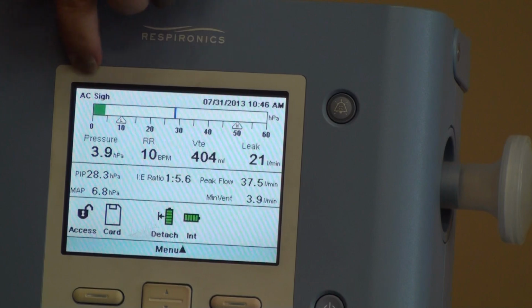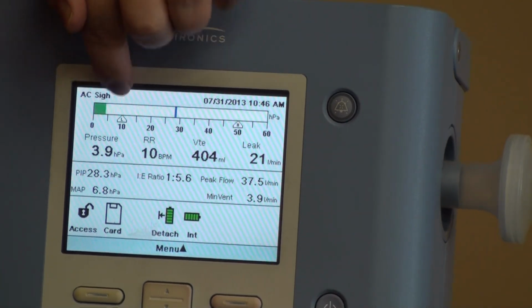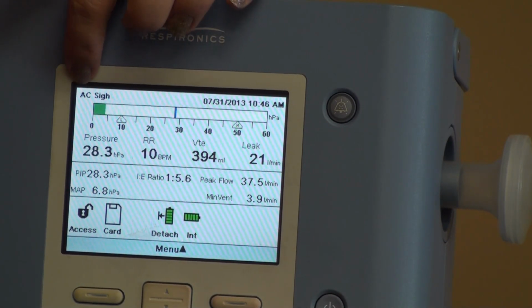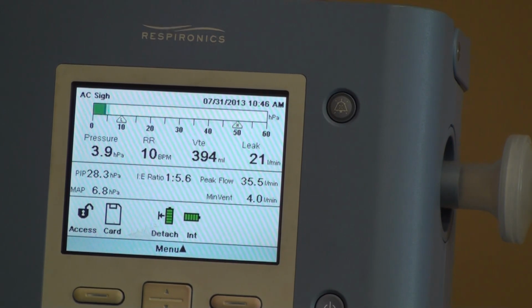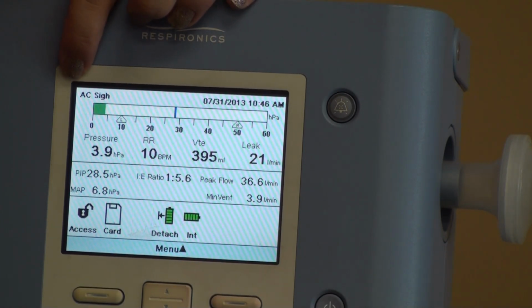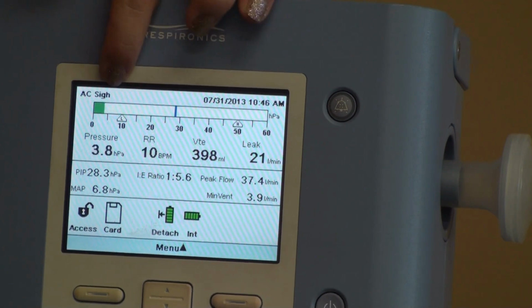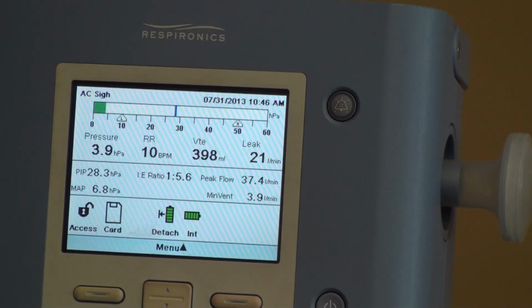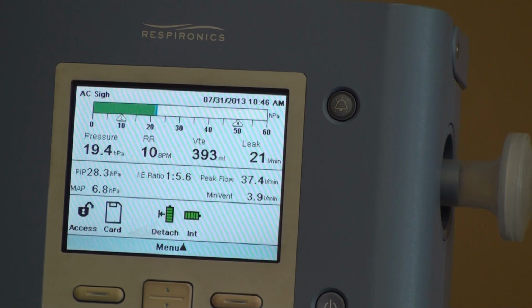B is going to be your prescription. That is this little piece over here. Now I have only one prescription in there. If I had more than one, because this machine has the technology to have 2 prescriptions, you have a primary and you can have a secondary. Your primary can be your main one that maybe you use all the time, and your secondary one might be one that you use at night only, or you use during weaning, or you're just using like CPAP trials or something like that. If I had 2 in here, it would say primary, or if I was running on my secondary, it would say secondary there. But it says nothing, so therefore it means I have 1 prescription in there.